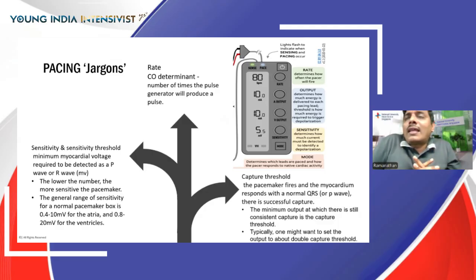The other two pacemaker jargons you need to be aware of are what we call sensitivity threshold and capture threshold. Sensitivity refers to the minimum myocardial voltage required to be detected as a P wave or an R wave. It's measured in millivolts, and the lower the sensitivity number, the more sensitive the pacemaker is. Essentially, it increases the sensitivity of the pacemaker. When you start using a pacemaker, you'll have to set the sensitivity threshold. I'll go through that in detail. But the general range of sensitivity for a normal pacemaker is about 0.4 to 10 millivolts for the atria and 0.8 to 20 millivolts for the ventricle.